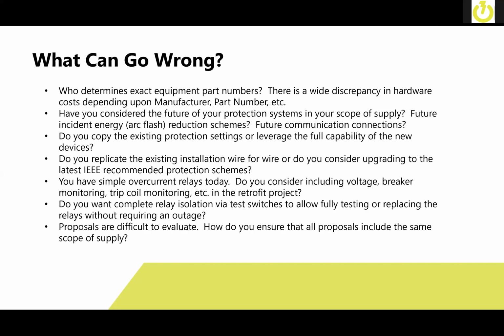You may have simple overcurrent relays today. Do you want to include the voltage, the breaker monitoring, the trip coil monitoring, et cetera, in the retrofit project? Do you want to consider maintenance switches that are also integrated into the system? Do you want to consider fast bus systems? Do you want complete relay isolation via test switches to allow for fully testing and replacing the relays without requiring an outage?